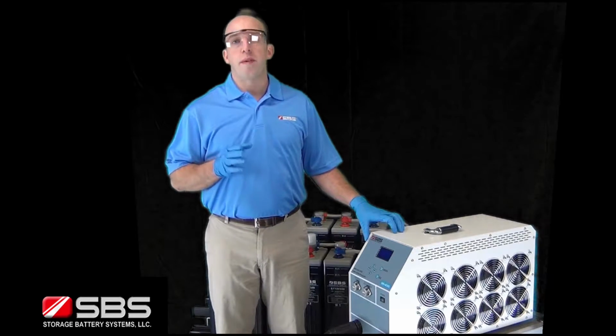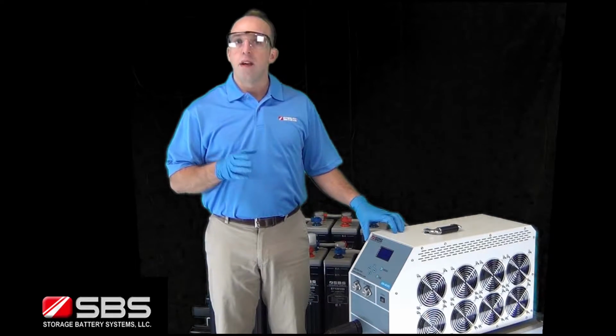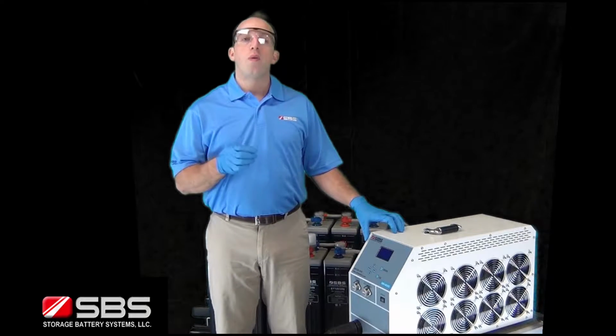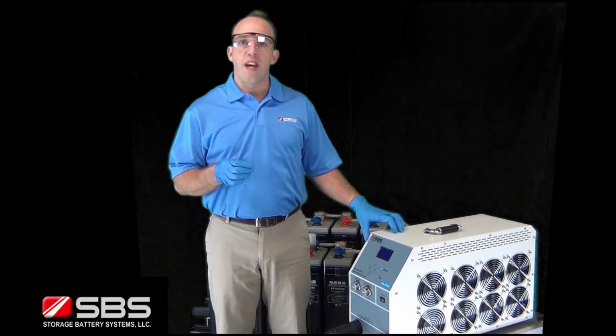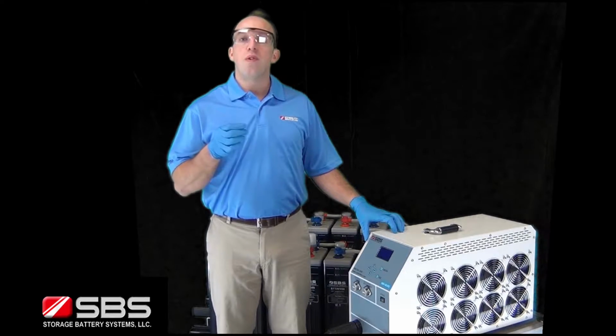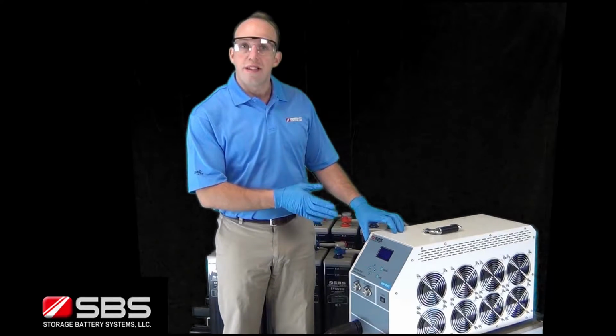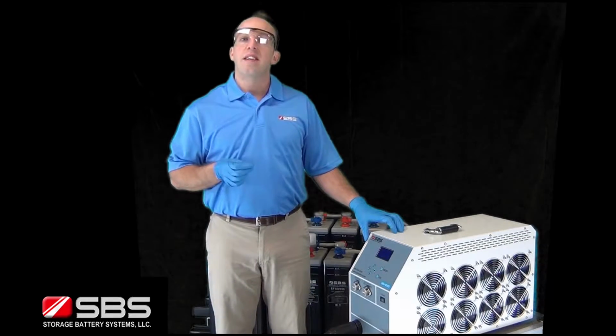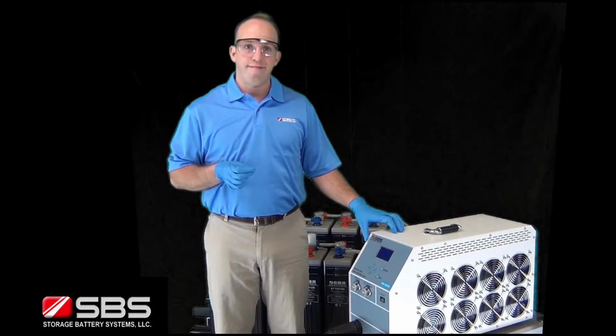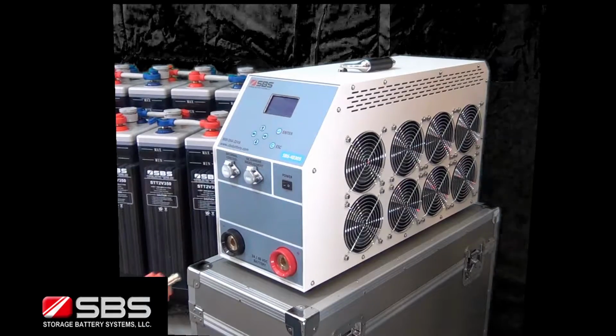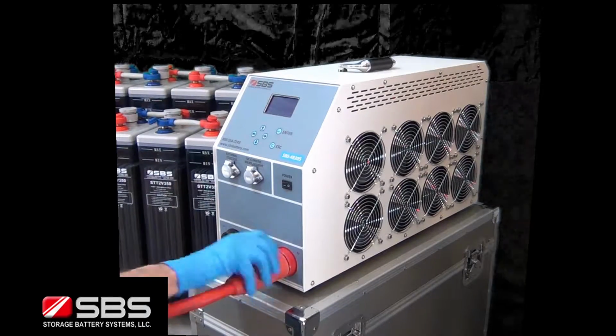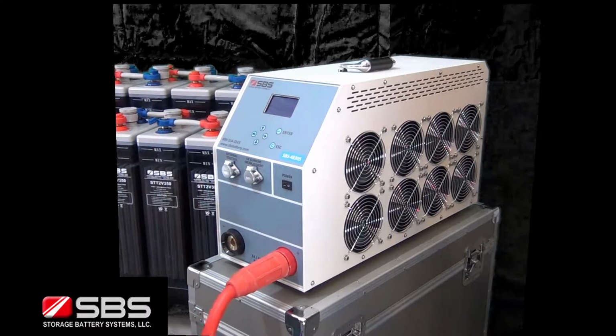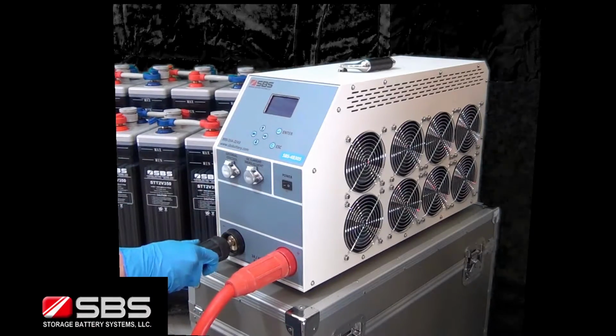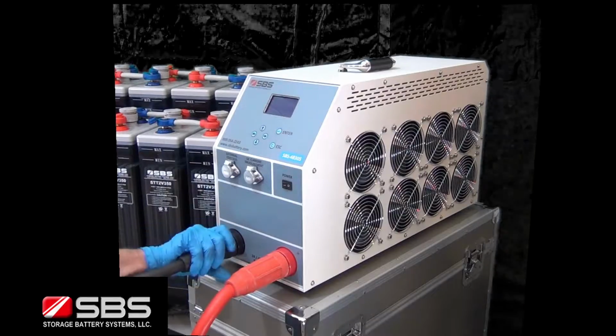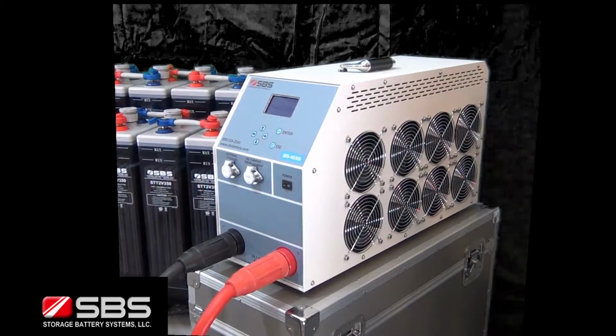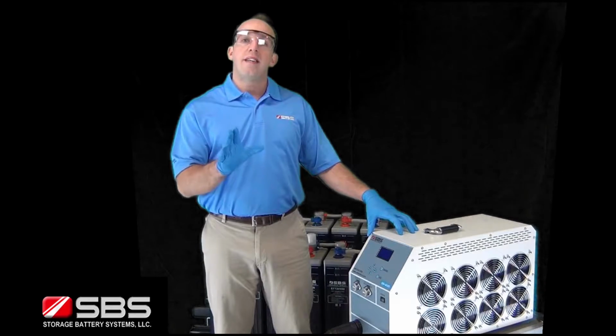First, let's run through some of the buttons of the SBS S-Series before we do our capacity testing. While running tests, the LCD screen will notify you about the battery state. You may use these control buttons, arrows, enter, and escape keys to navigate the menus displayed on the LCD screen. Near the bottom of the load bank are the load cable sockets into which you will insert the provided cables. These cables are the main tester connections while performing tests. The cooling fans are visible on the side of the load bank unit. Make sure that there is adequate room for airflow and heat dissipation.